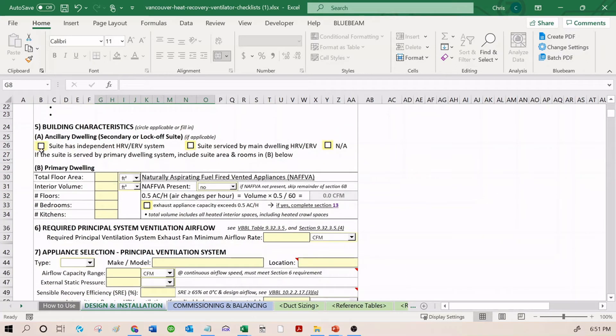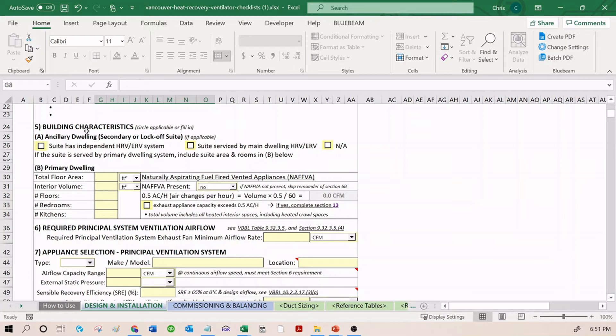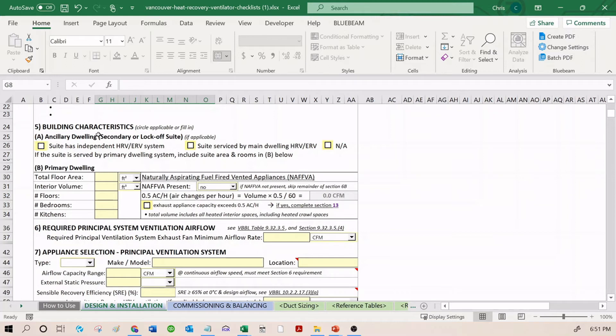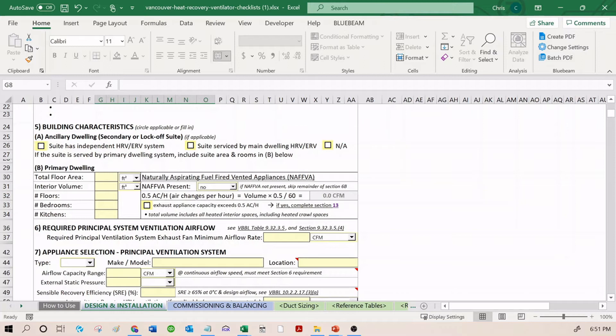Building characteristics: if you have a legal suite in a home and the suite and the dwelling unit are both served by the HRV, you only require one of these checklists to be submitted. It's one ventilation system, one checklist. If you have different HRVs serving each unit, then you need to submit a checklist for each ventilation system. So if I have one HRV in my main dwelling and one HRV in my legal suite, I should submit one of these for my main dwelling and one of these for my legal suite.